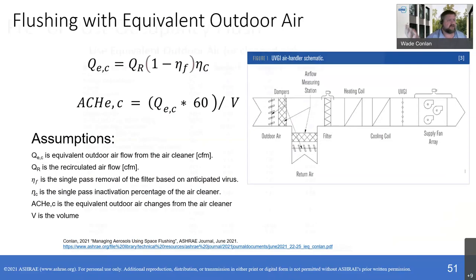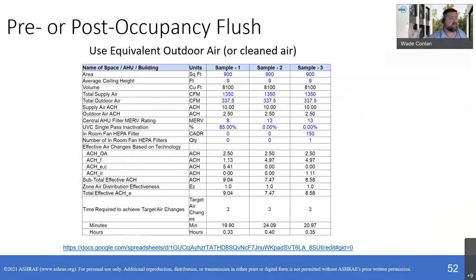And then this shows the actual calculation table, right? There's a couple tabs in there. In this scenario, I picked a typical classroom. It's a middle school classroom size. It's just an average size that people are aware of. 900 square feet, 9-foot ceiling height. Anywhere that is blue text, you're going to put in the supply air changes and then your outdoor air changes, right? And you can see that it's the same room with three different samples.